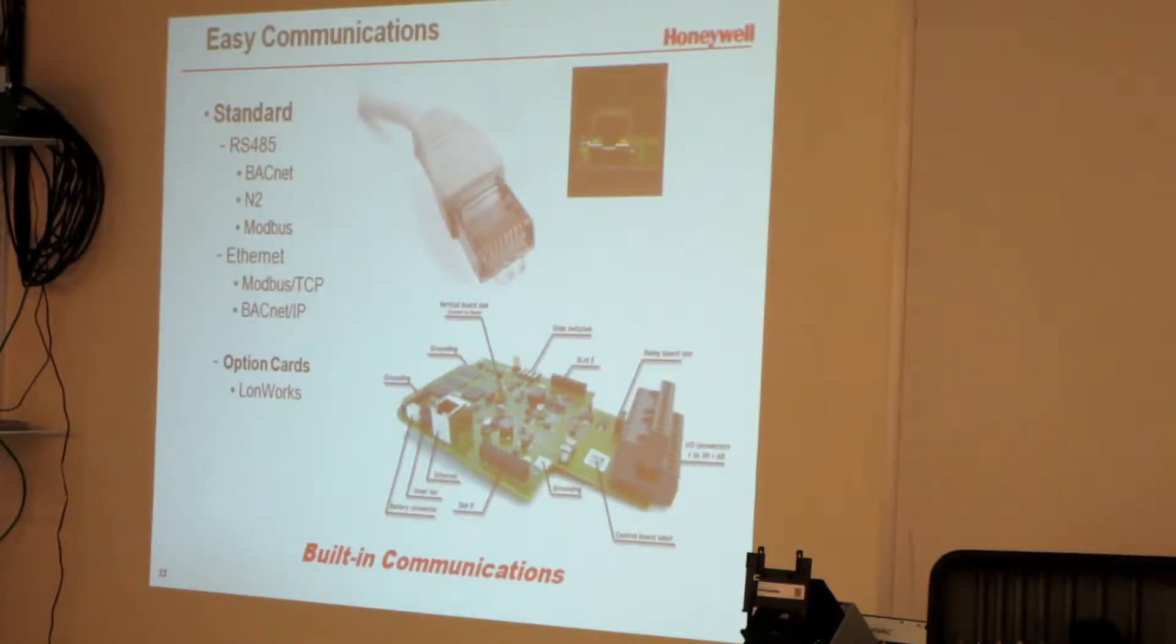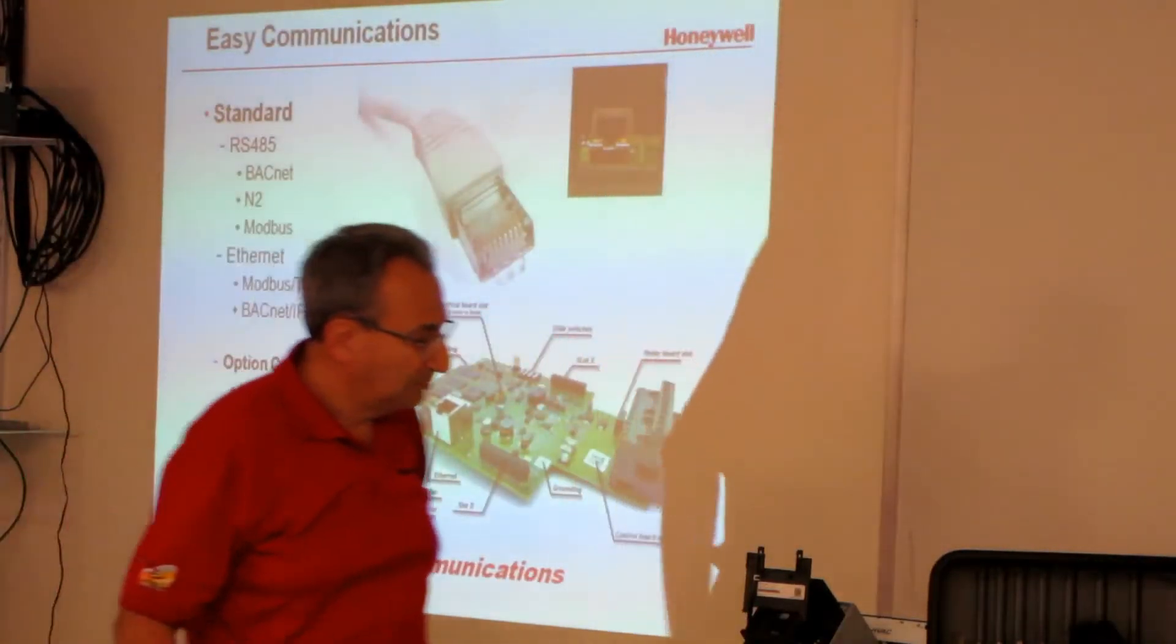The communication: RS-485, BACnet, N2, Modbus, those are all built in. So if you're using Modbus or Johnson N2 or BACnet, it's there. There are instruction books for each of those communication protocols that are standalone. Ethernet, Modbus or BACnet over Ethernet, and there's an Ethernet plug right here.